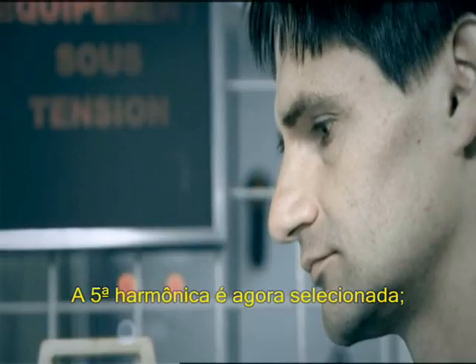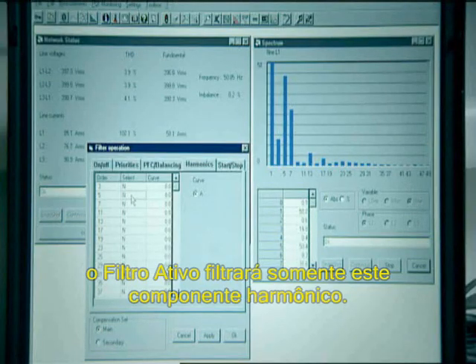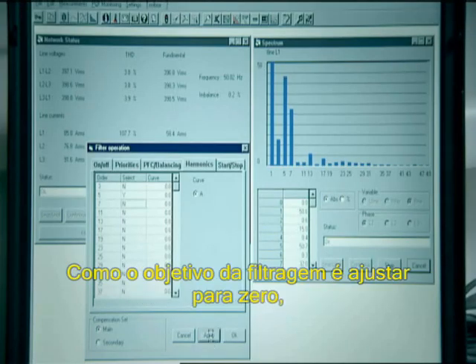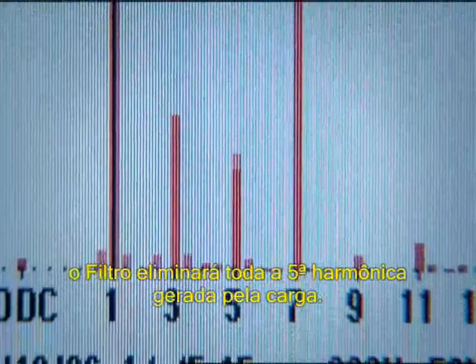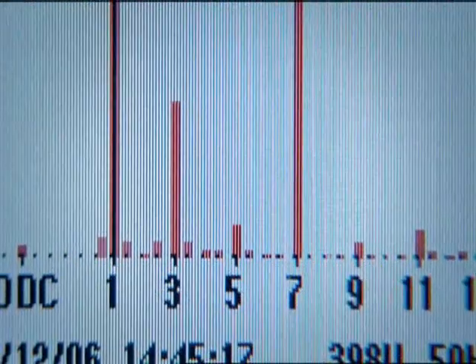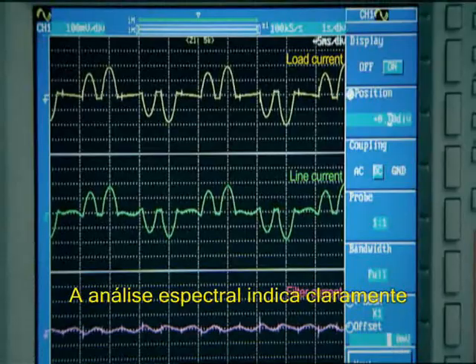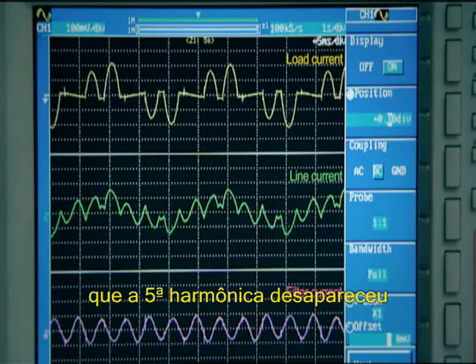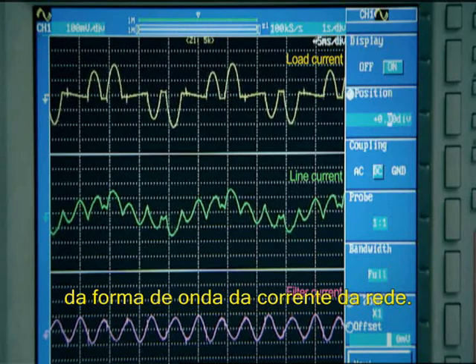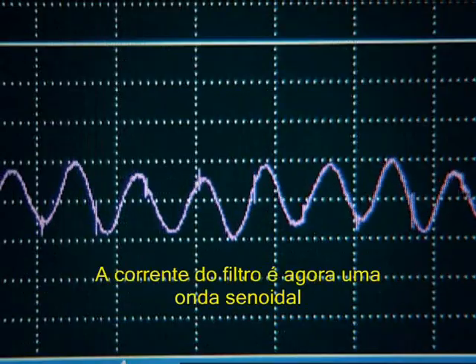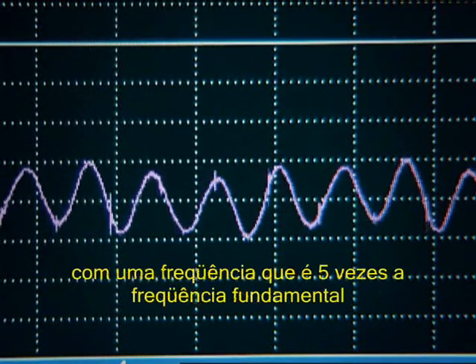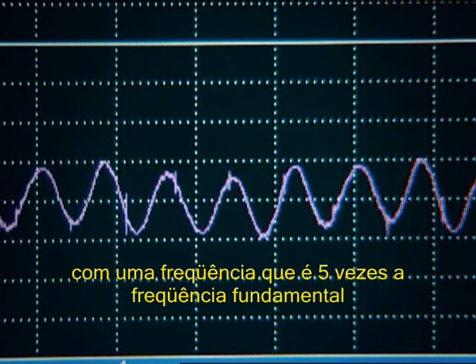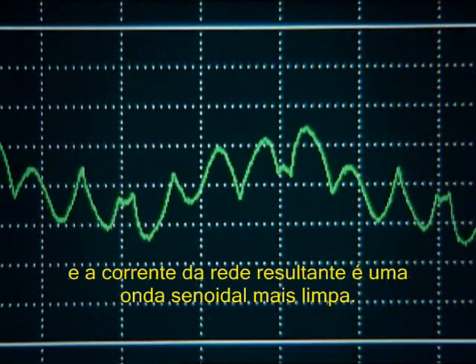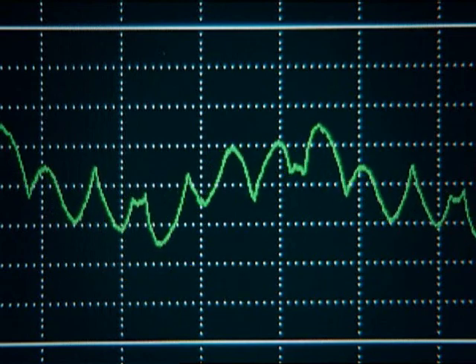The 5th harmonic is now selected. The active filter will only filter that harmonic component. As the filtering target is set to 0, the filter will take out the entire 5th harmonic generated by the load. The spectral analysis clearly indicates that the 5th harmonic has disappeared from the line current waveform. The filter current is a sine wave with a frequency which is 5 times the fundamental frequency, and the resultant line current is a cleaner sine wave.